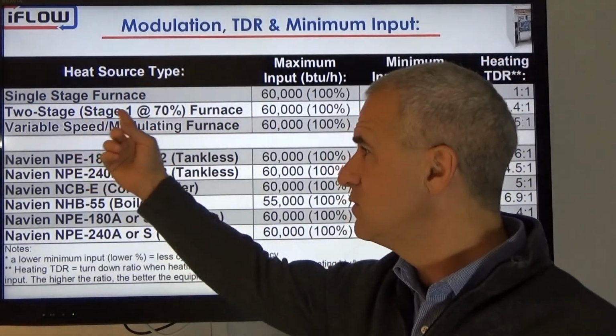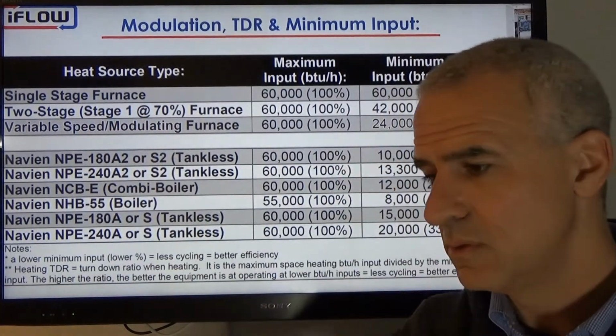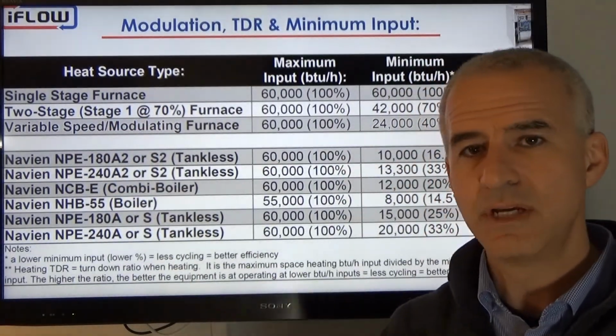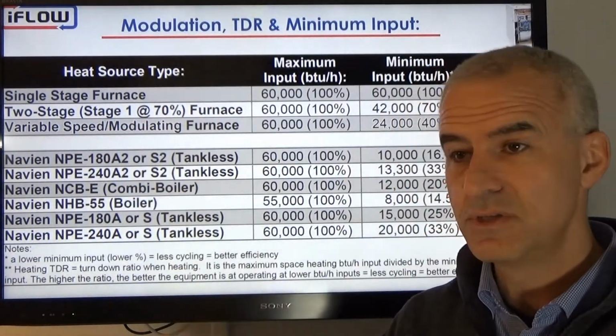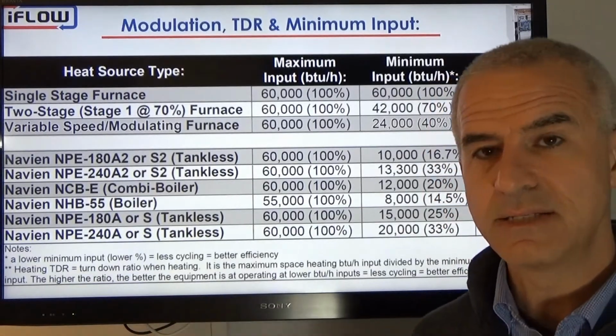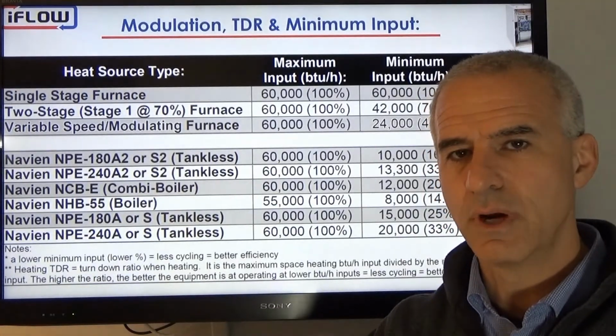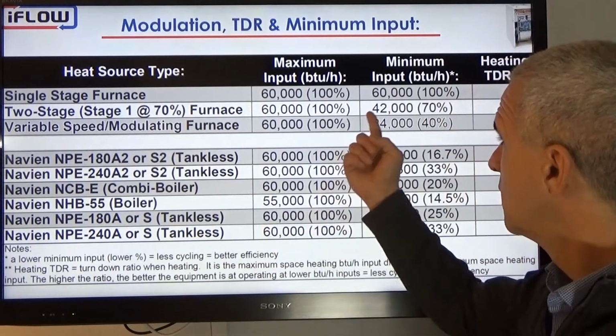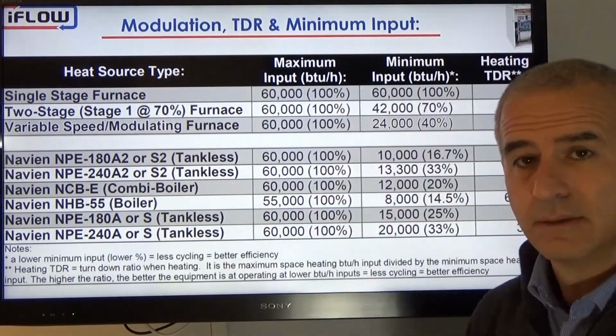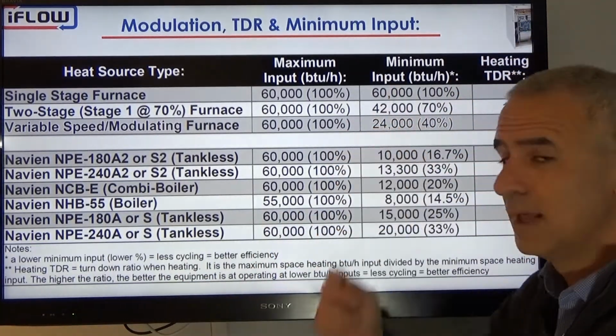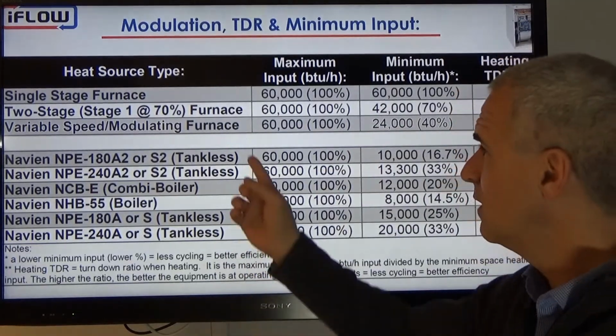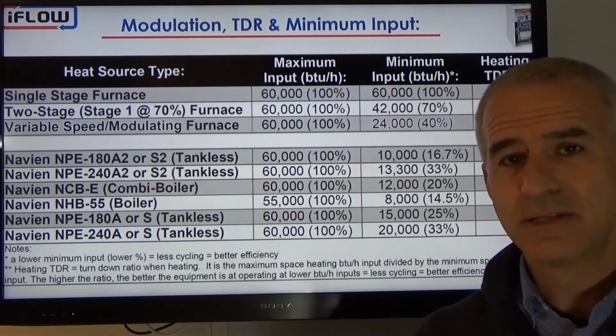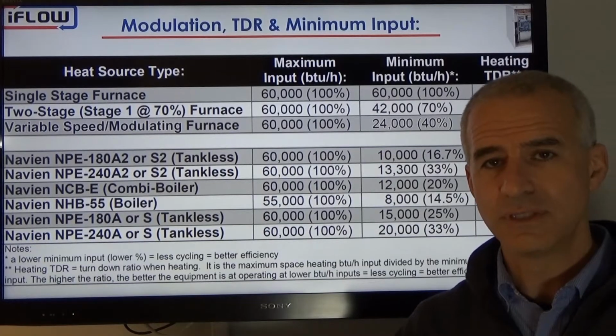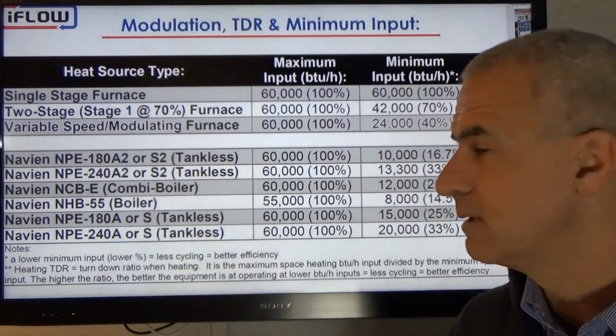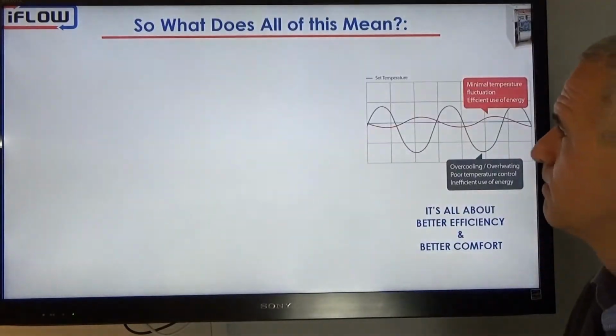And on the contracting side, I've talked to so many contractors that think a 2-stage furnace with an AFUE of 96, 97 is a great furnace, great option for the homeowner. Well, the numbers don't tell us that. The numbers say that the minimum input is still too high, even on the best modulating furnaces, for new construction today, or if you're doing a deep retrofit. So let's look at what that means.